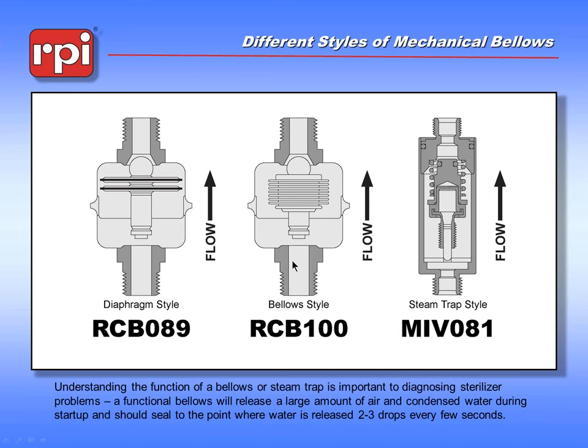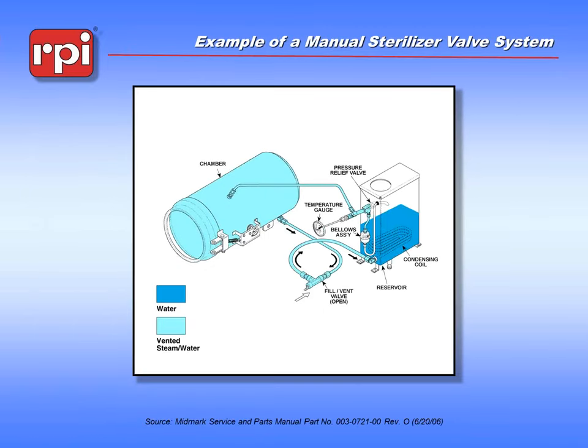This is the bellows as originally produced by Midmark. We also offer an upgrade — a multi-convoluted bellows. This device needs to move each of the bellows less distance; it works the same way based on the expansion rate of a fluid contained within the bellows, but because it moves each bellows less distance it's more reliable and has a smaller temperature window between opening and closing. Also used in the same way is a device called a steam trap, which has a slug of wax with a known expansion coefficient that expands, moving a rod into a sealing surface and interrupting the flow of air and steam.